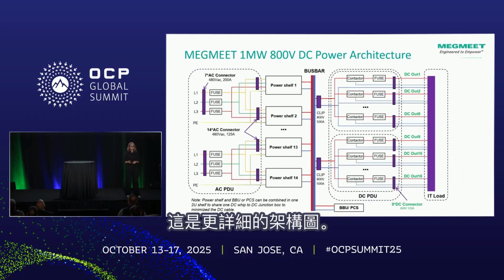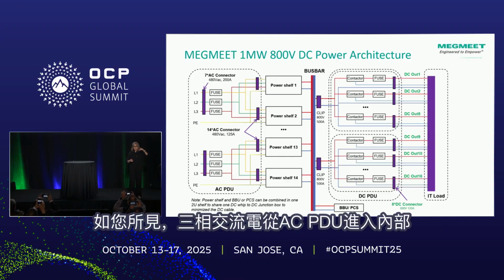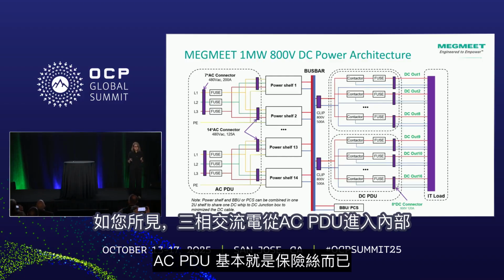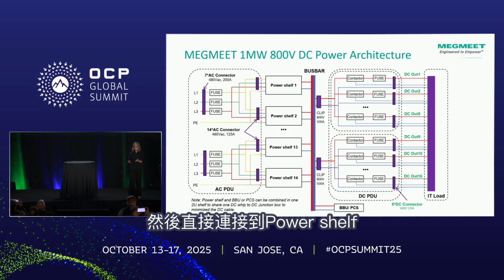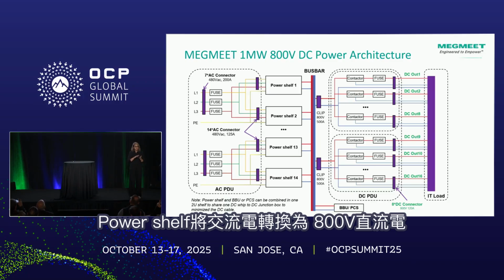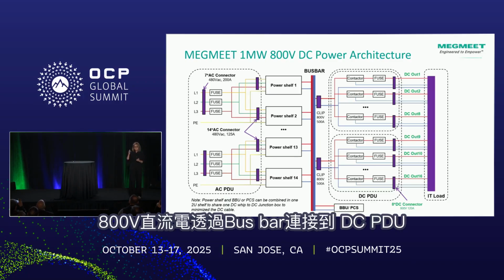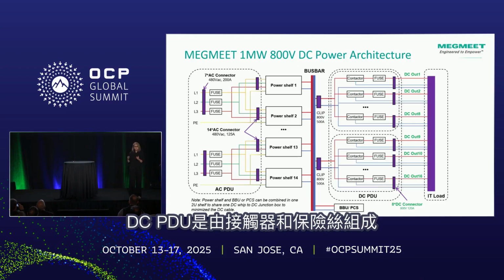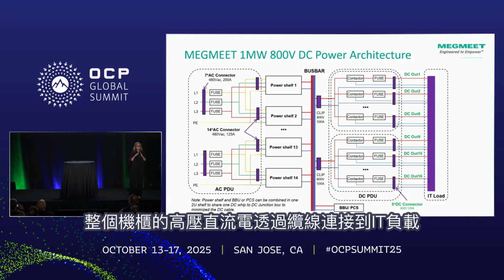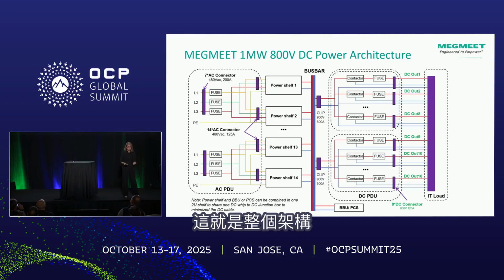This is a more detailed structure of the architecture. So as you can see, the 3-phase AC comes in inside the AC PDU, which is basically fuses. And that goes directly to the power shelf. And as you can see, power shelf converts the AC to 800. 800 on the bus bar is also directly connected to the DC PDU, which is contactors and fuse. And from this whole rack, the HVDC cables are going to the IT load. This is basically the whole architecture.